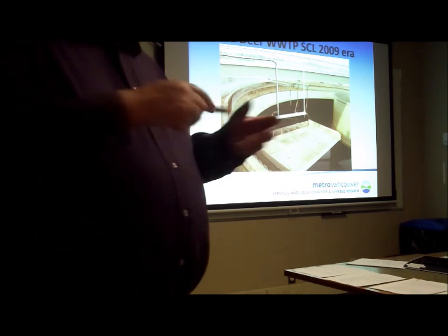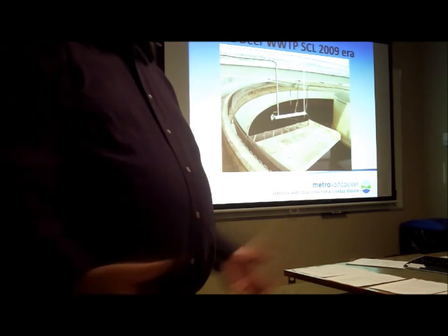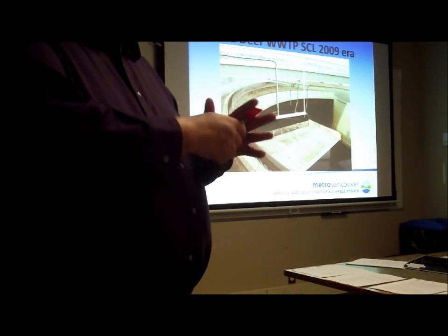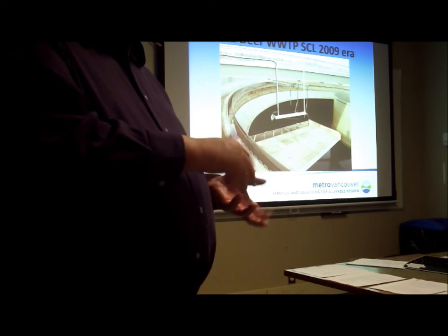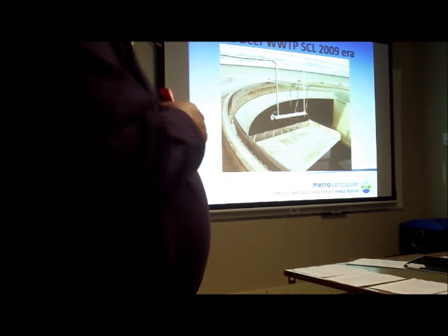One thing I wanted to show, I drew a very crude diagram here. Pardon my artwork. But most of our clarifiers now use a suction header. We pump it. That gives us better control. Like, if we want to return our sludge at 45%, we can actually use a VFD and maintain that, which gives us better control.